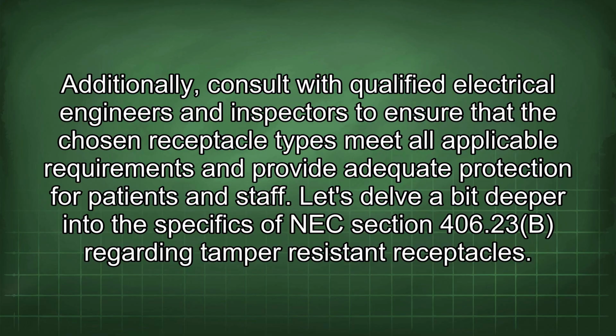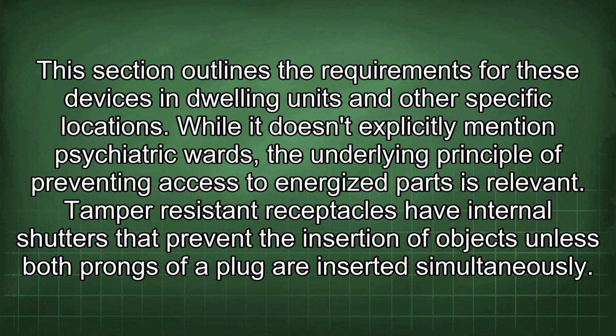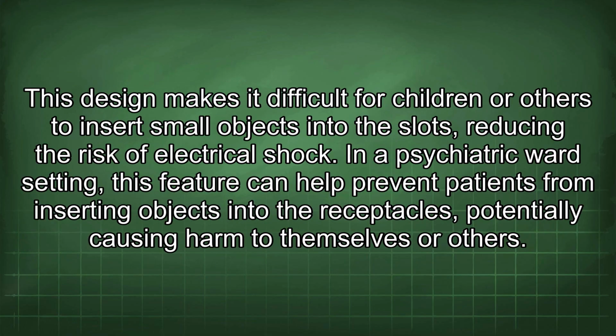Let's delve a bit deeper into the specifics of NEC Section 406.23b regarding tamper-resistant receptacles. This section outlines the requirements for these devices in dwelling units and other specific locations. While it doesn't explicitly mention psychiatric wards, the underlying principle of preventing access to energized parts is relevant. Tamper-resistant receptacles have internal shutters that prevent the insertion of objects unless both prongs of a plug are inserted simultaneously. This design makes it difficult for children or others to insert small objects into the slots, reducing the risk of electrical shock. In a psychiatric ward setting, this feature can help prevent patients from inserting objects into the receptacles, potentially causing harm to themselves or others.